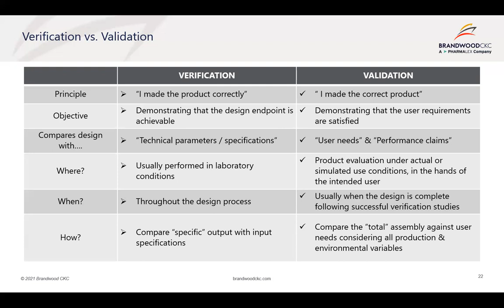One of the best ways to complete those verification and validation activities, obviously each of those activities can be discrete and address specific requirements. But again, traceability through design and development is very important to make sure that you've addressed all requirements that you've identified at the beginning of the process. And the best way to do that is really to maintain a traceability matrix.